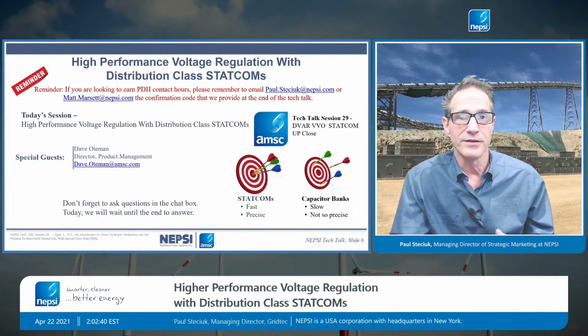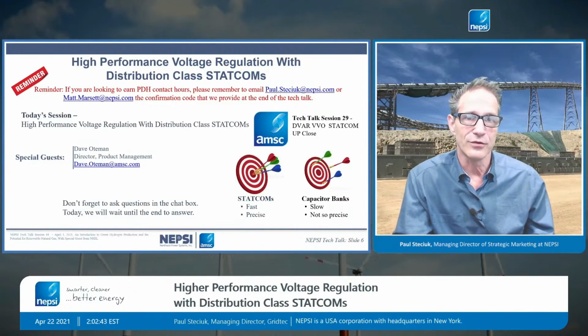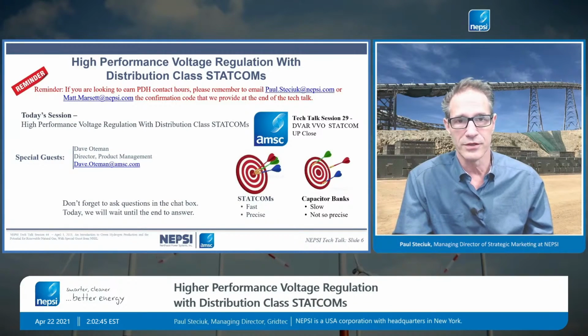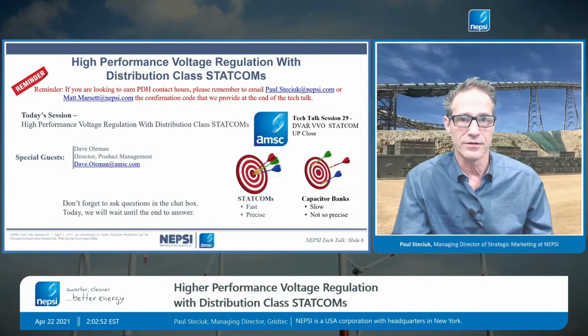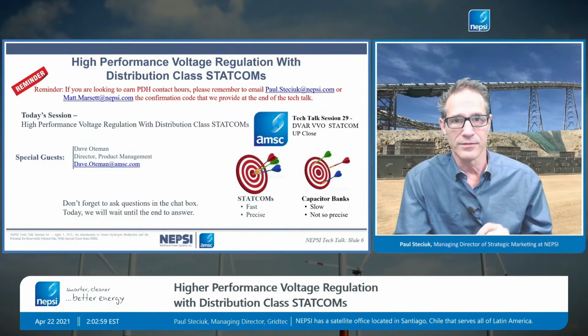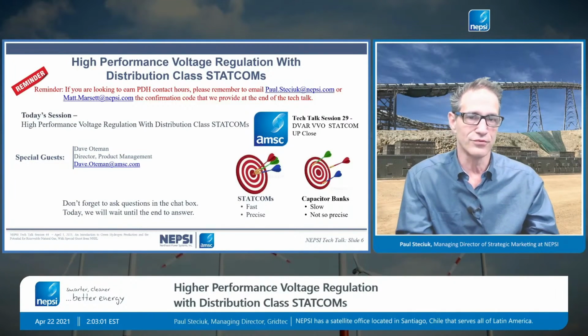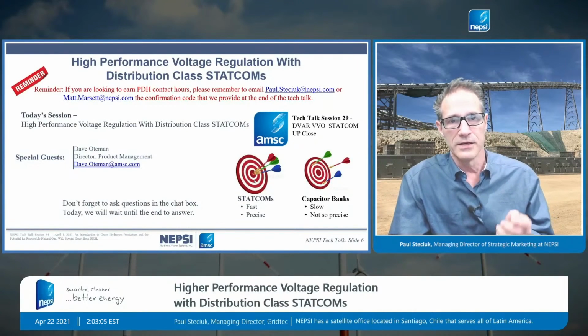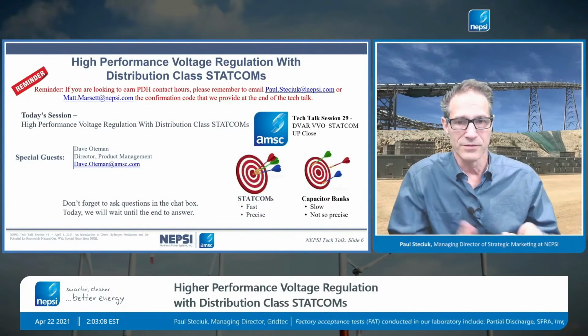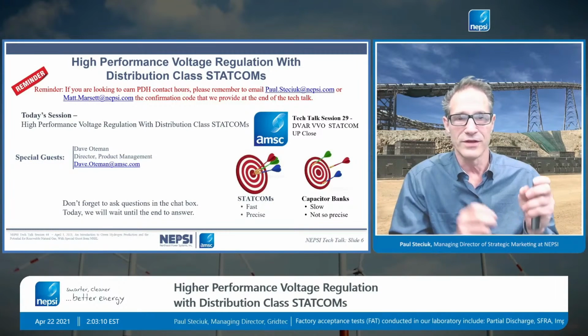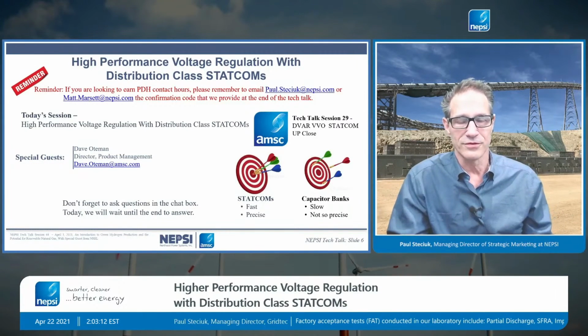We first met Dave on Tech Talk session number 29, where we covered the D-VAR VVO STATCOM system up close. During that presentation, he discussed how the STATCOM could be used for motor starting and what this VVO STATCOM is. Remember, one of the key things about STATCOMs is they're fast and precise. I have a little symbol here for that. And capacitor banks, which is what NEPSI produces, are more of a slow and not so precise device.